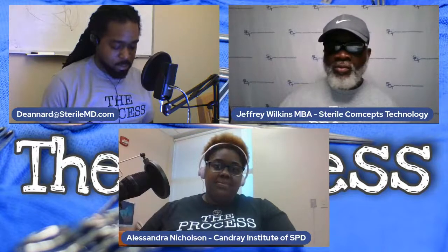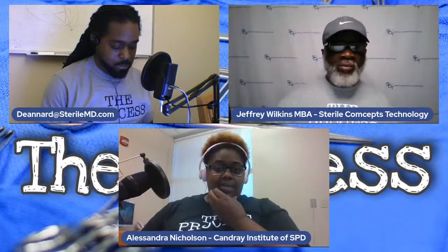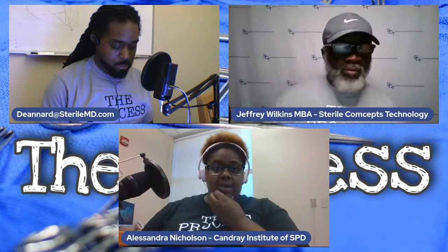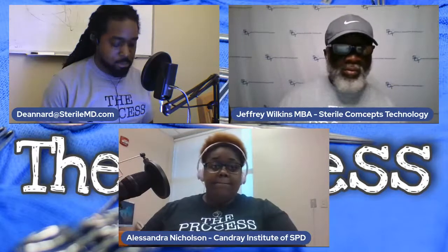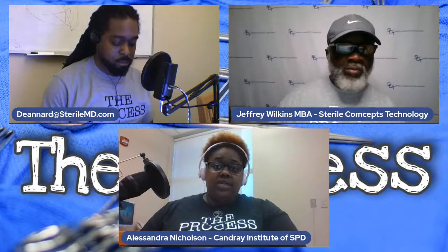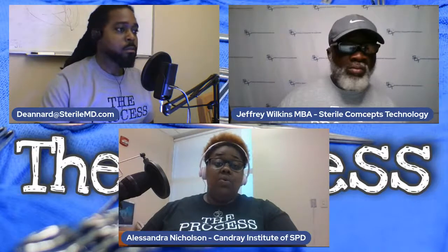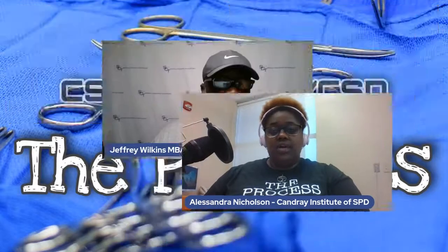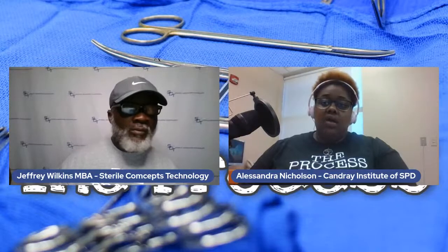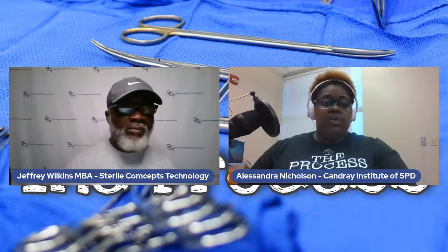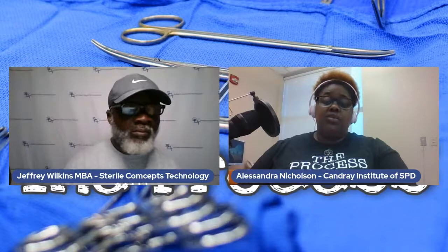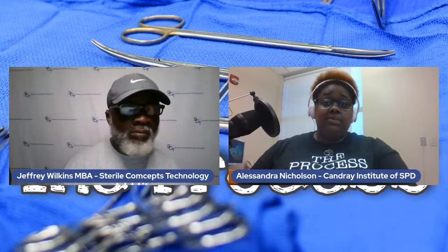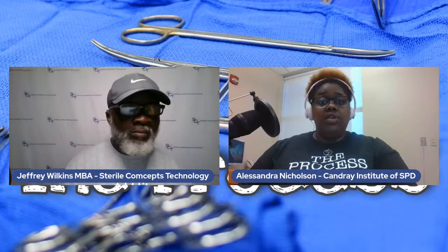Definitely 100%. Just a couple extra little things on IFUs for my new techs that may not be aware. When you're looking at those, you're going to see your temperatures in Fahrenheit or Celsius. So make sure you know what your machine is set for so that you can do the conversion if you need to. Also look out for any type of special information. Like sometimes it may tell you what an exposure time is, and then it may give you what the maximum is, which means that you are actually in a position where you can go over if you need to.